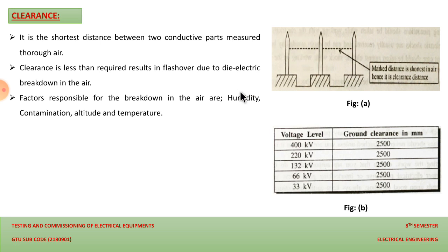Altitude and temperature also matter, depending on whether the air is dry or moist. If the air is moist, the chances of flash-over between two electrodes is more. If there is dry air, we can keep the electrodes as per standard distances. But if the air is moist, we should keep the electrodes according to standards that follow the atmosphere of that place.